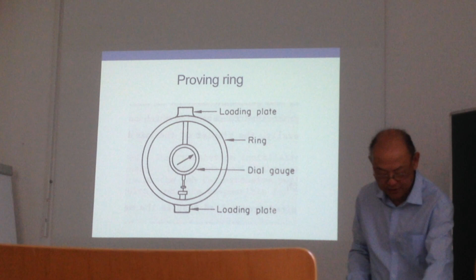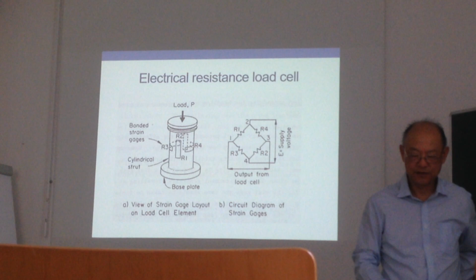You see this four strain gauge alignment. Again, this is the same idea as a Wheatstone bridge to offset the temperature effect, and in this case it also offsets off-center loading. This is a very commonly used force measurement device today.